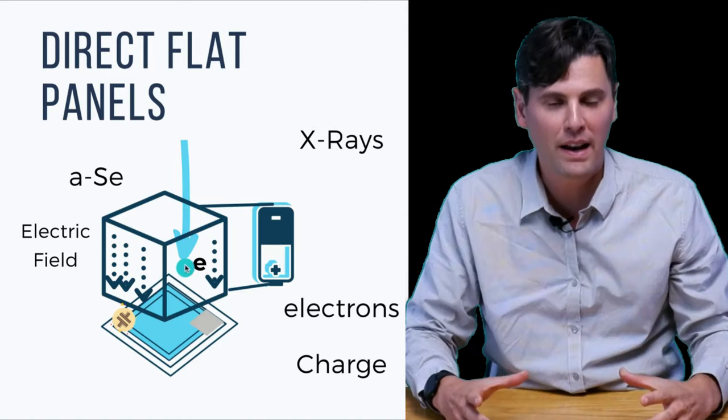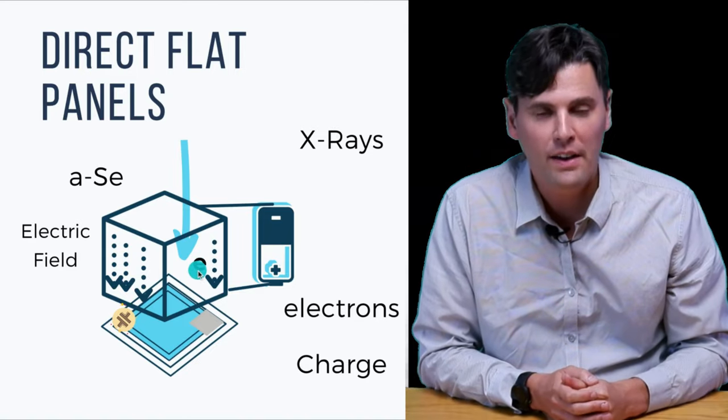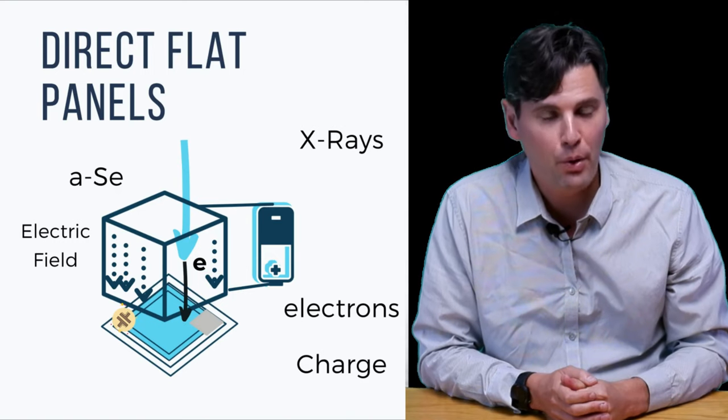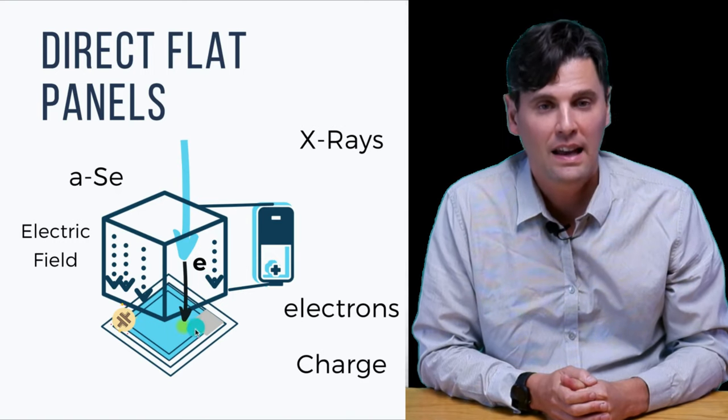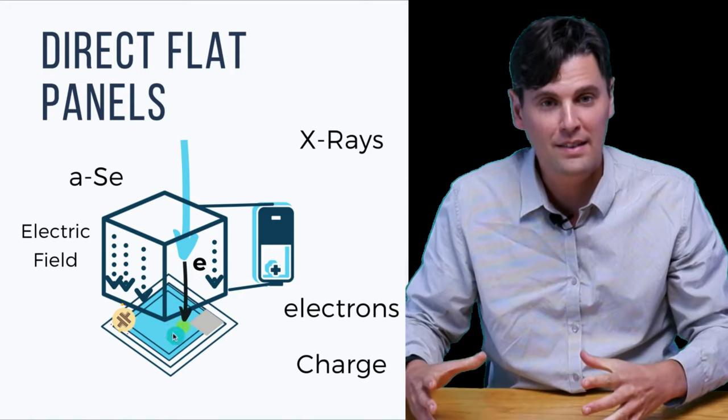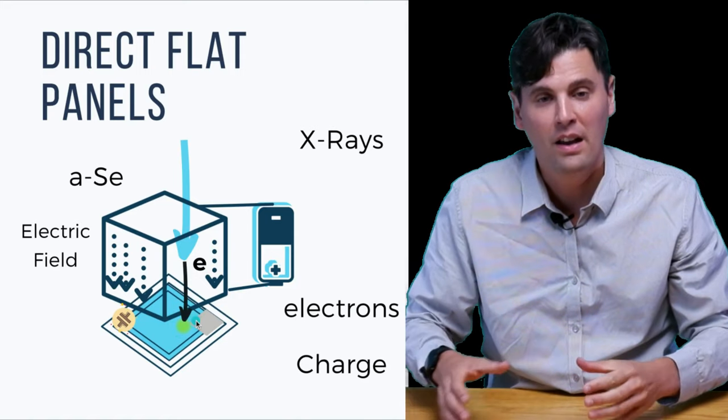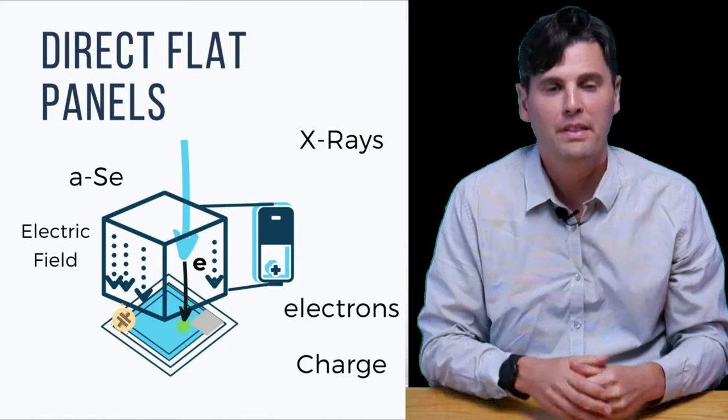The major advantage of direct DR flat panels is higher spatial resolution. The electrons coming down are pulled relatively directly and don't spread out, whereas light photons spread out in both the cesium iodide and gadox cases — less so with cesium iodide, but spreading still occurs. The direct panel has the clear advantage in spatial resolution because of minimal electron spreading.